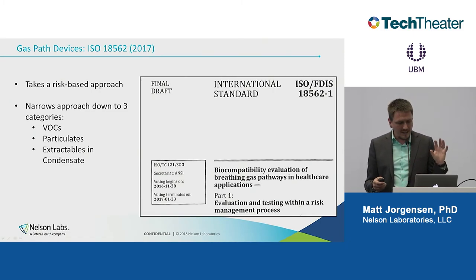18562 is great because you're using a risk-based approach. You really just look at what can actually reach the patient that would affect them—the volatiles carried by the gas and any particulates that could be carried by the gas. So you really just focus on those two things, the volatiles and particulates. To me, it makes a whole lot of sense.